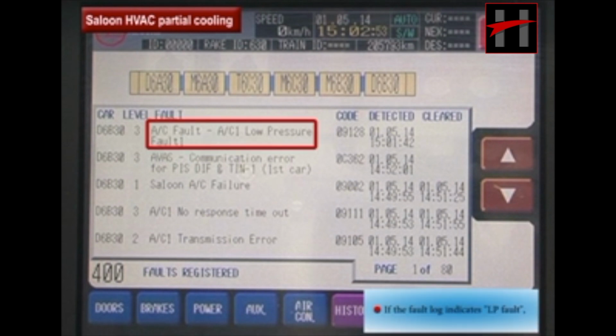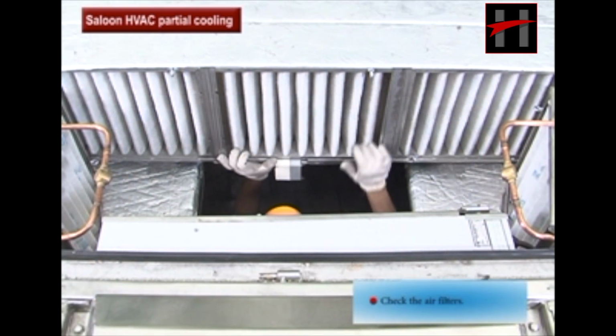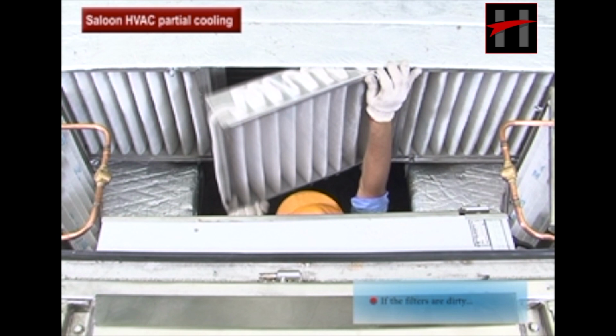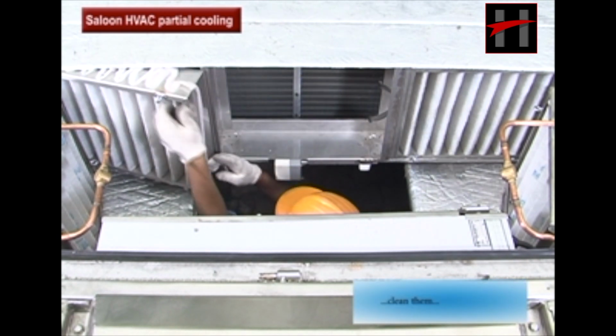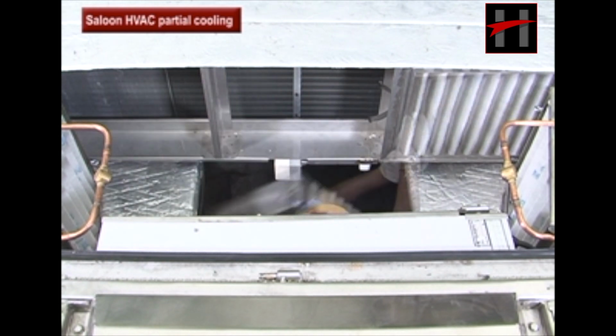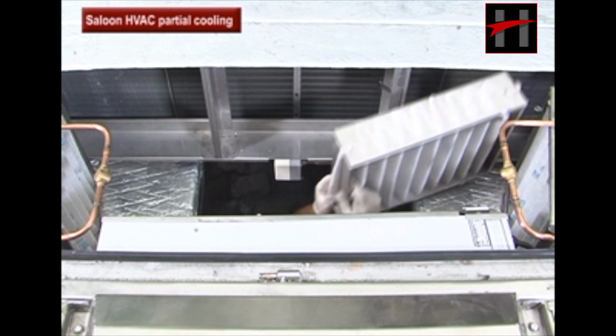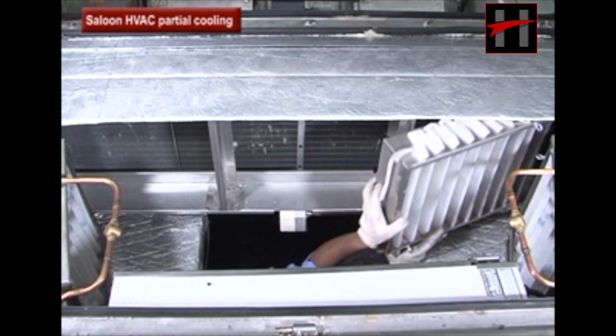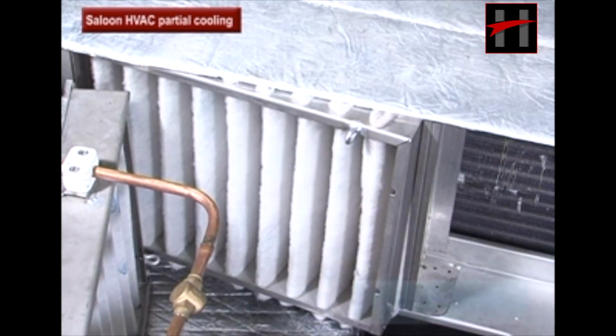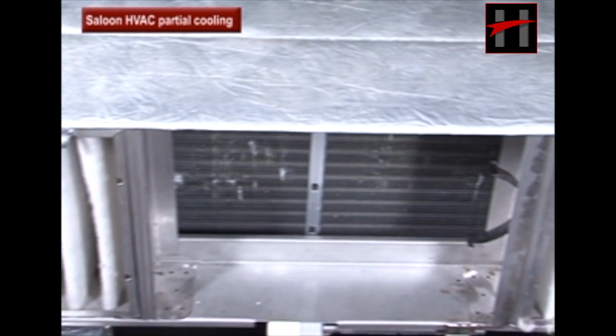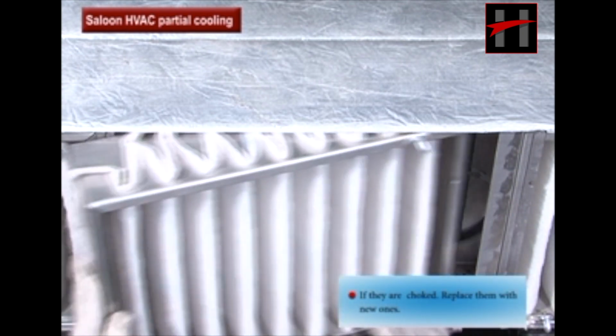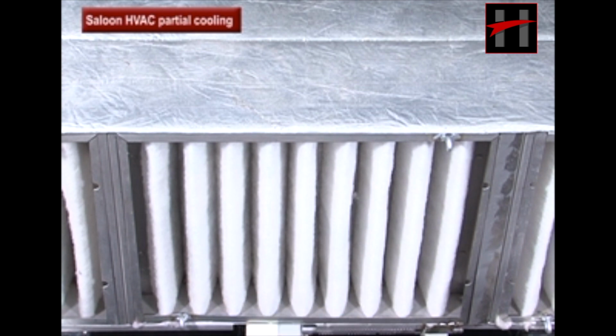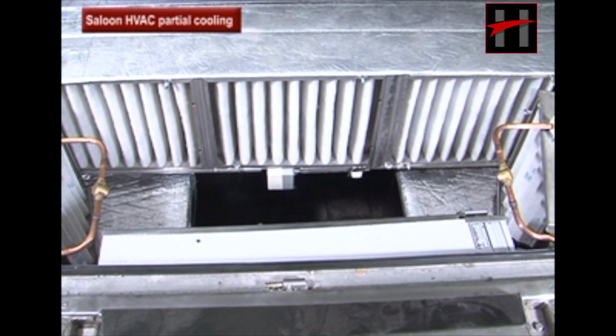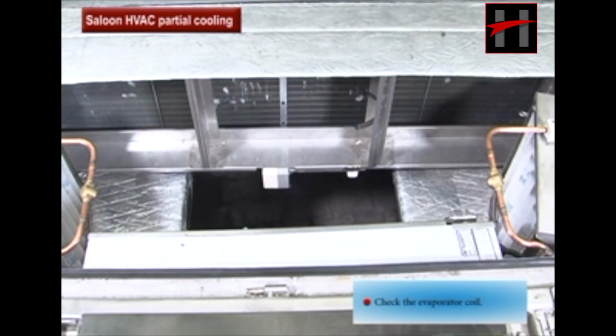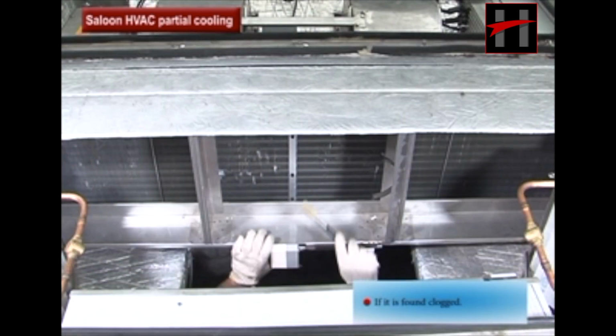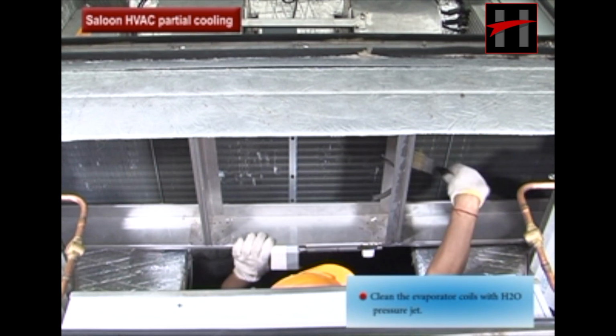If the fault log indicates LP fault, check the air filters. If the filters are dirty, clean them and refit. If they are choked, replace them with new ones. Check the evaporator coil. If it is found clogged, clean the evaporator coils with water pressure jet.